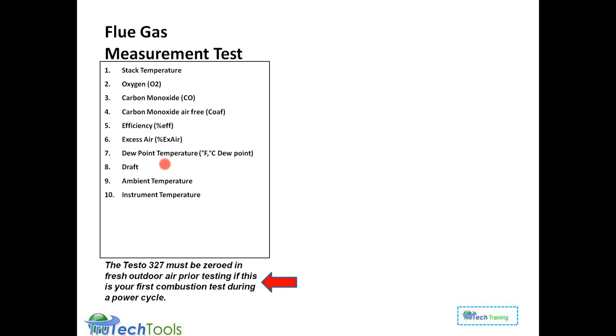That might be interesting if you're looking for issues where you have a system that isn't supposed to be condensing, but you may get below the dew point temperature. When that happens, then there's the chance that you could get some of that acid gas to rain out of the flue gas and cause some issues inside either the equipment or the vent system, the chimney, et cetera.